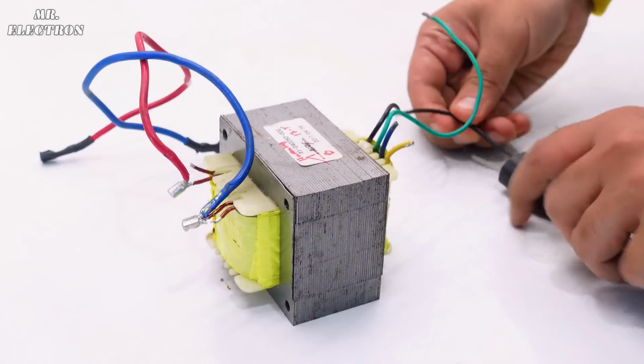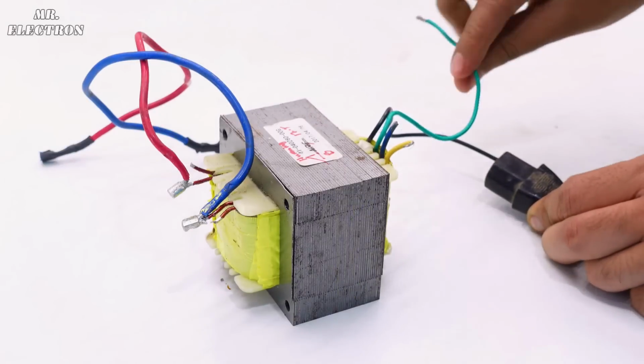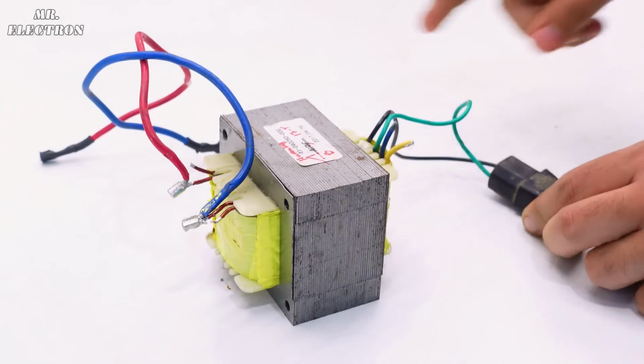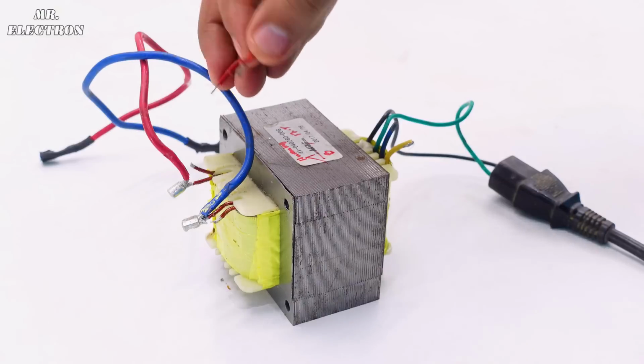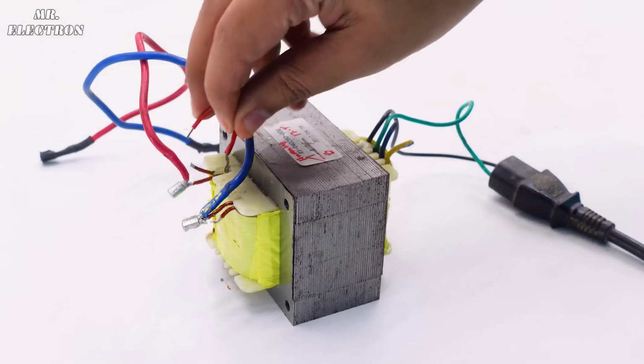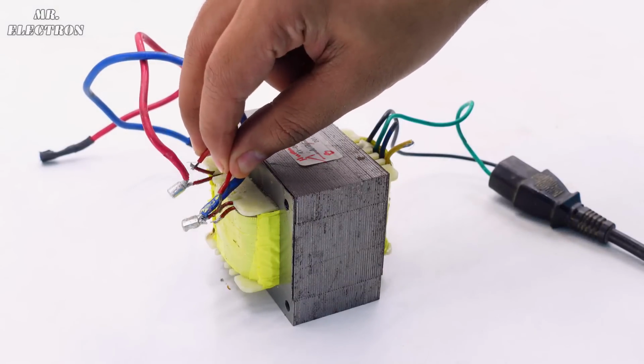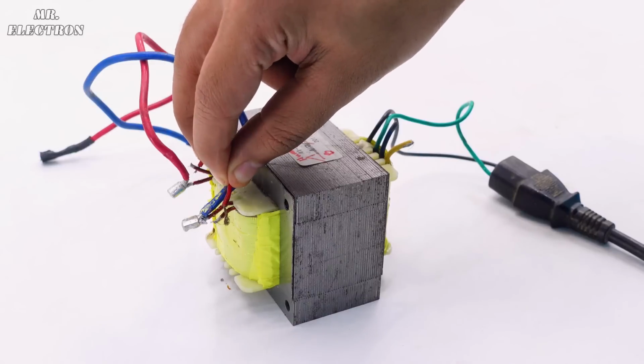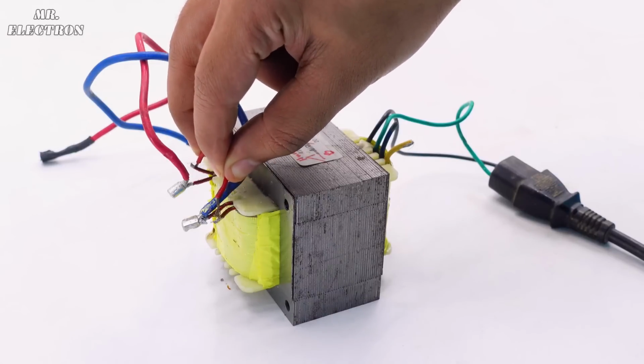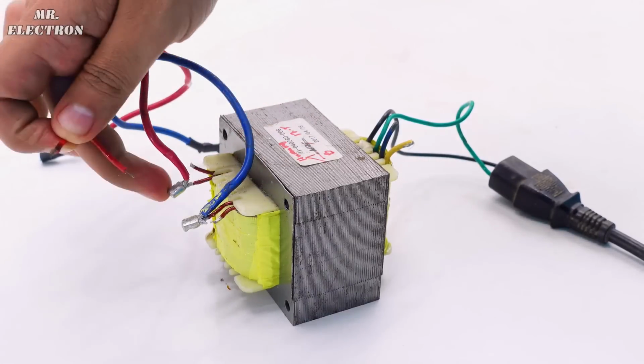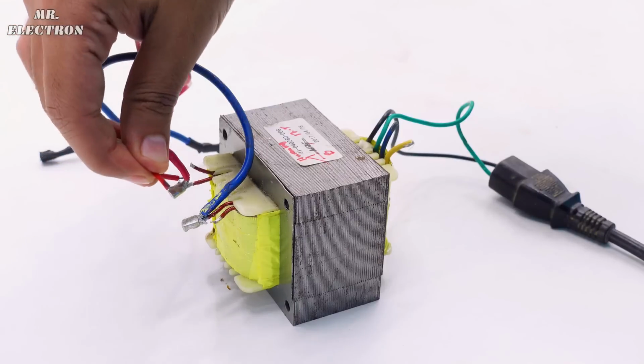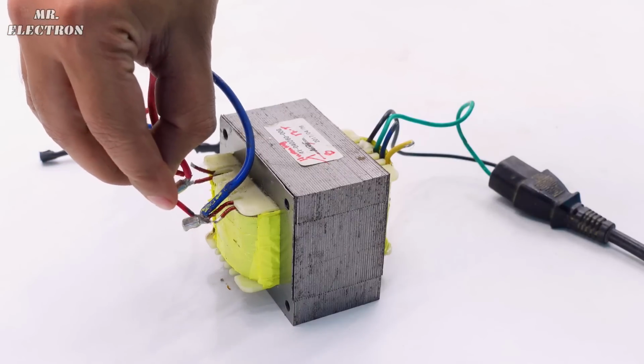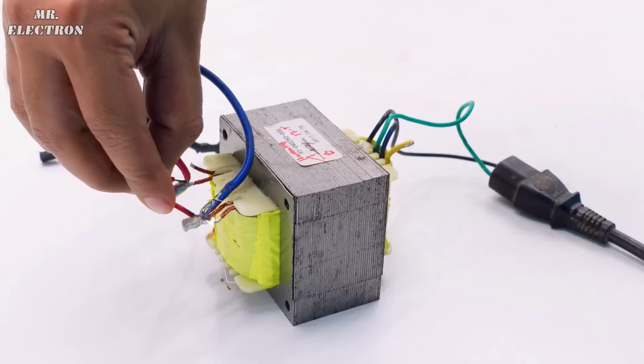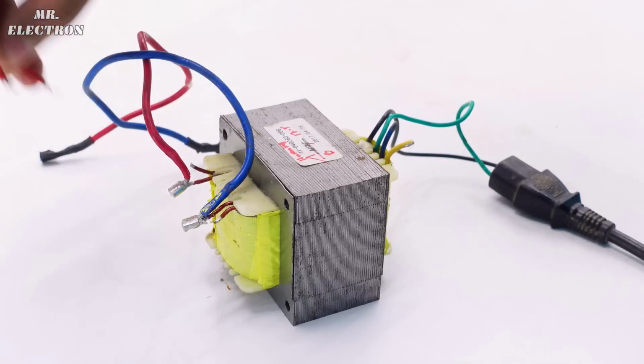Next, connect the 220 volt supply to the transformer input and turn it on. Now comes the part of finding out if I have disconnected the correct wire, and for that, simply short the new cutoff wires. If there is no sparking, then you were lucky. And if I would have cut off this other wire, let's check. See, so I was lucky, and I disconnected the correct wires.